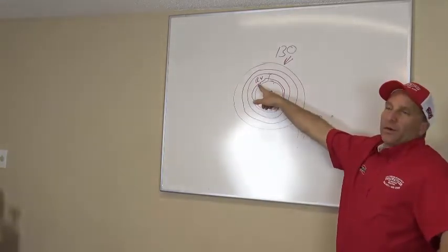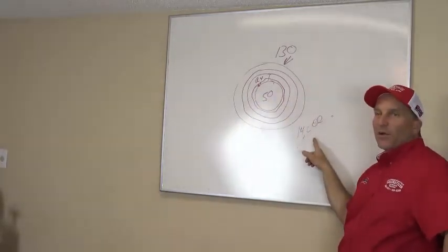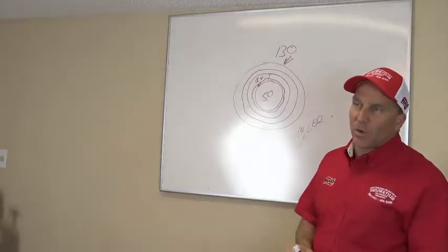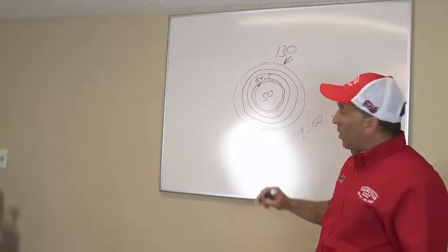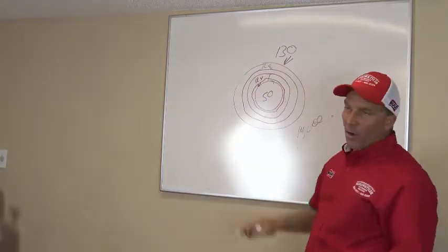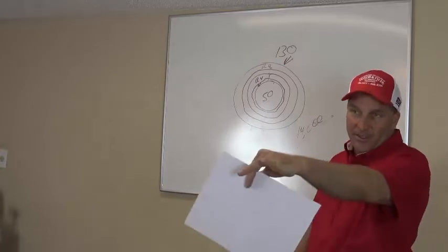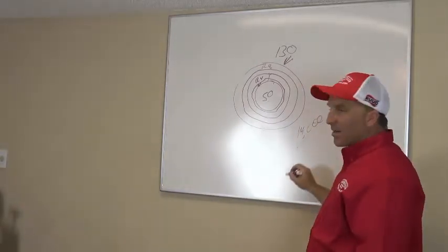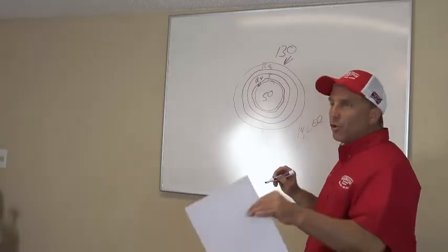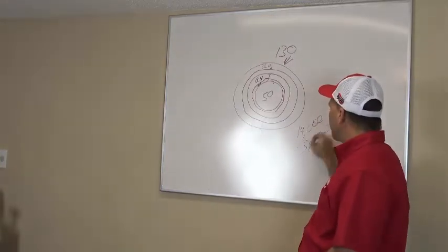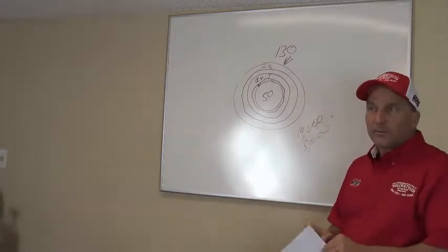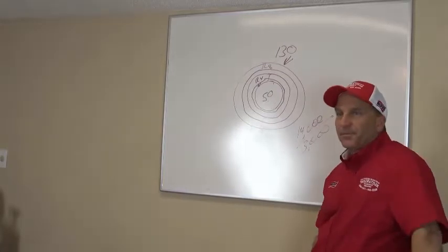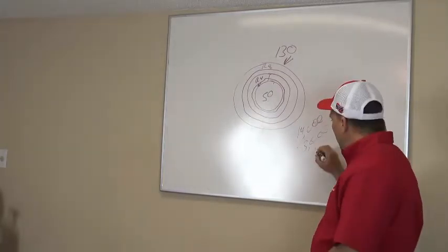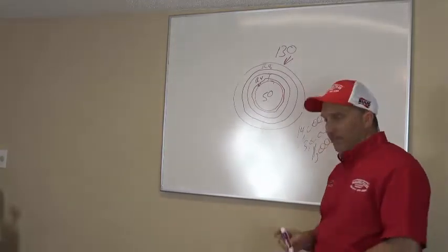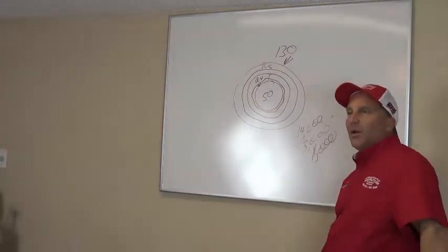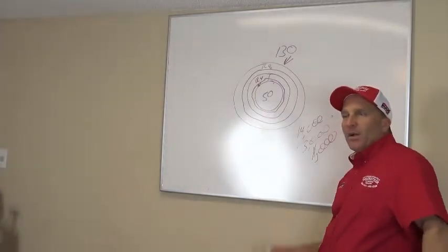I got R1 ductwork. 14,000 BTUs to cool my ductwork. Let's go ahead and re-insulate your ductwork, sir. If I re-insulate your ductwork, I'm going to put R8 value ductwork on that. I'm going to just re-wrap everything, just like y'all did the other day, right? Okay? I'm going to cut the amount of BTUs it takes to cool your ductwork down to about 3,000 BTUs. It's still going to take some BTUs to cool it, but I'm going to cut it down to 3,000. I just saved you 11,000 BTUs, right? I saved you almost a ton of air conditioning by re-insulating your ductwork.